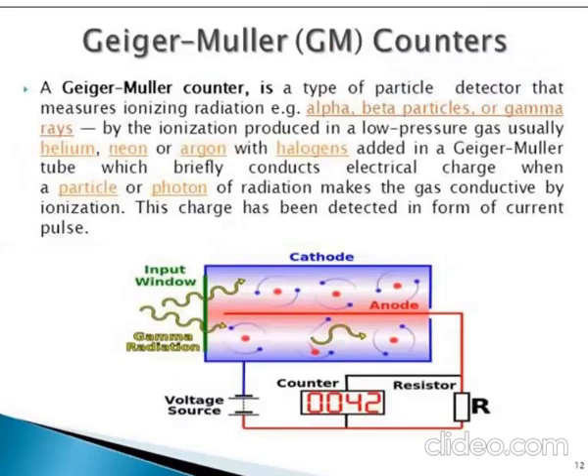The Geiger-Müller (GM) counter is a particle detector which measures ionizing radiation — whether alpha, beta, or gamma. It produces ionization in a low-pressure gas, usually helium, neon, or argon with a halogen added inside the GM tube. The tube briefly conducts electrical charge when a particle or photon of radiation passes through, making the gas conductive by ionization, and the charge produced is detected in the form of a current pulse.